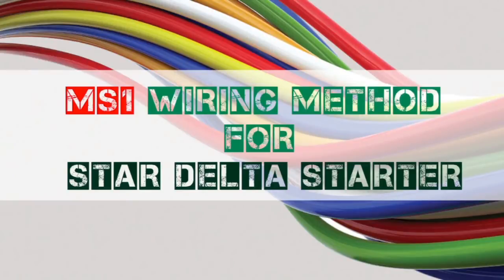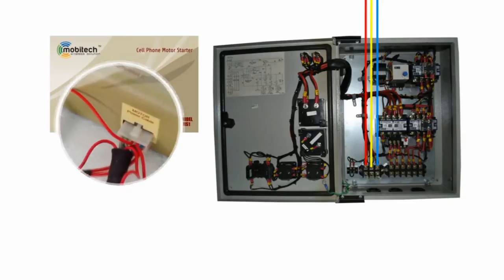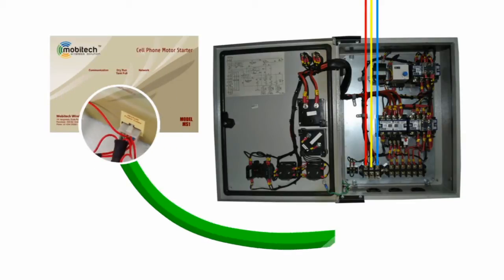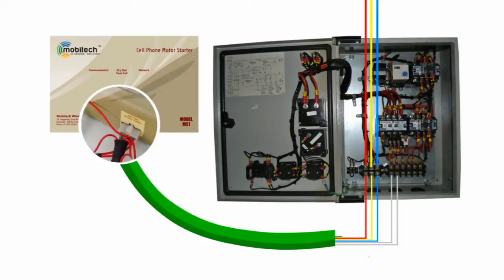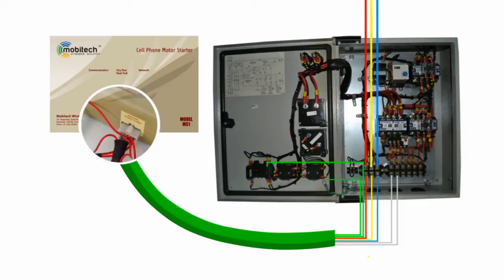Wiring method for star delta starter. Connect red wire to R phase, connect yellow wire to Y phase, connect blue wire to B phase. Connect grey color wire to motor output, connect green wire parallel to ON button, connect one of the red wires to OFF button.